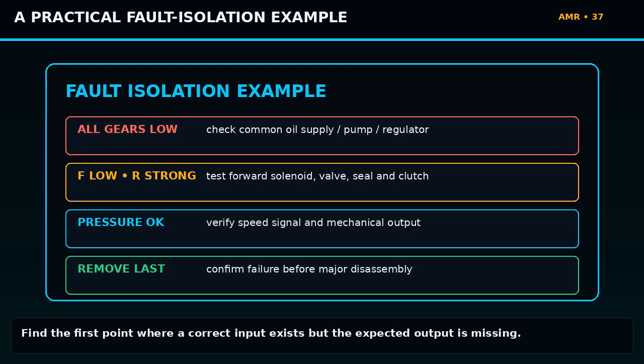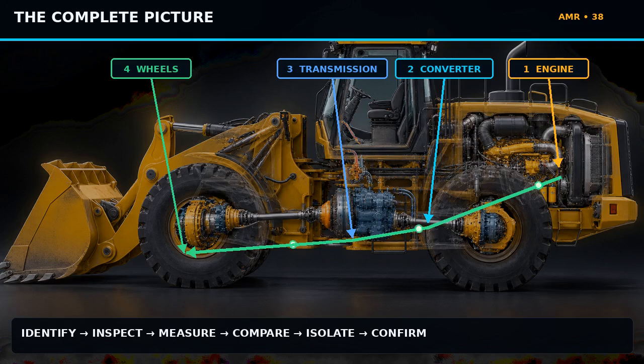Finally, if pressure is correct but the reported turbine speed jumps impossibly, inspect the sensor and target before removing the converter. Common inputs first, individual circuits second, mechanical removal last. The complete system is now one logical chain.